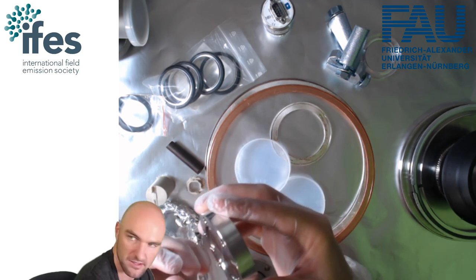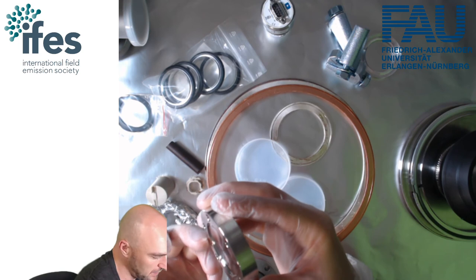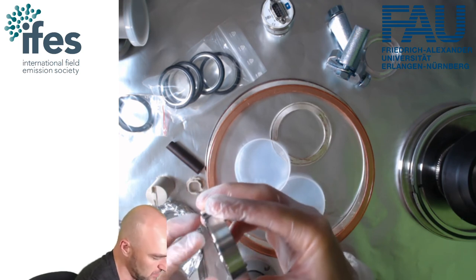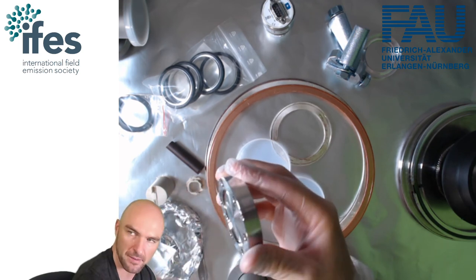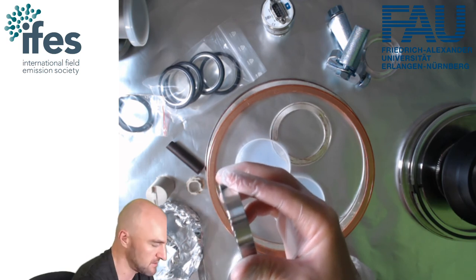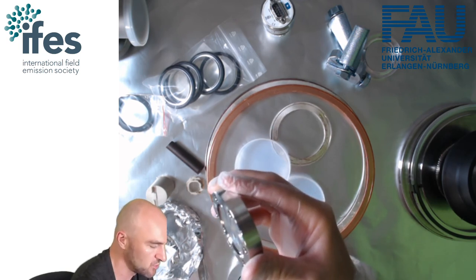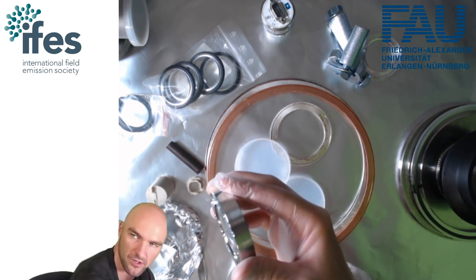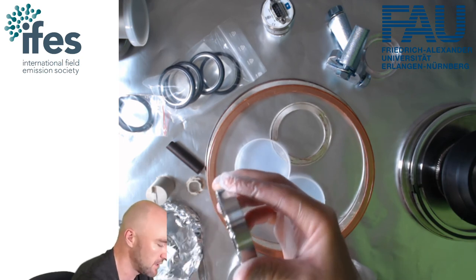So if you leak test your system, it can blow helium in from the bottom, it will escape from the top, and then you have a pump pumping out the system and detecting if any helium got into the system. Or you can do it in reverse and put helium into your system and see if it comes out.